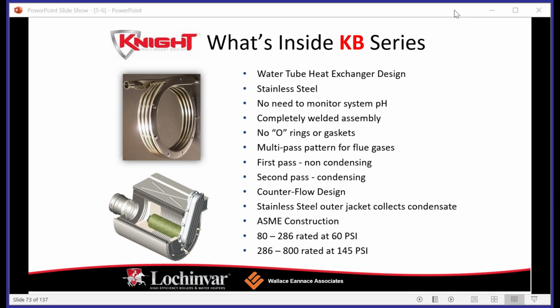Okay. Again, this is a stainless steel system. All of the heat exchanger you're going to see on the condensing equipment is going to be stainless steel. So why don't we use copper for condensing boilers? Well, as we discussed before, the condensation that's created by capturing that latent energy does create that caustic or acidic condensate. So only stainless is going to be able to stand up to it, and it will not corrode over time. Again, the heat exchangers are all ASME certified.